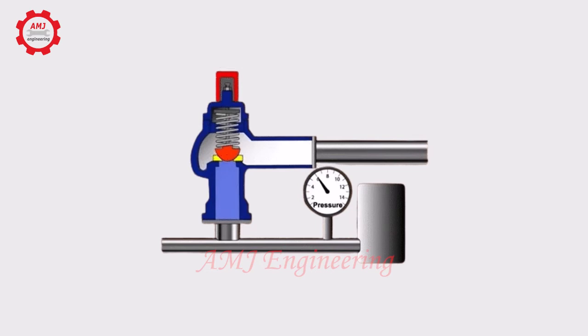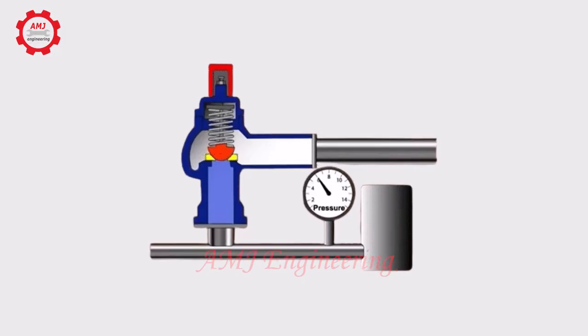In a normally closed relief valve, the force exerted by the compression spring exceeds the force exerted by system pressure acting on the ball or poppet. The spring holds the ball or poppet tightly seated.